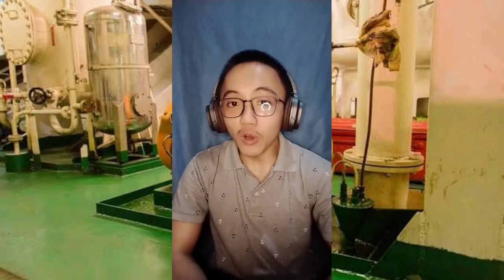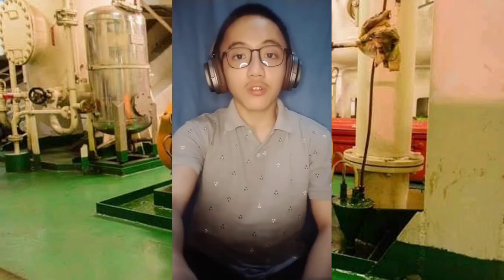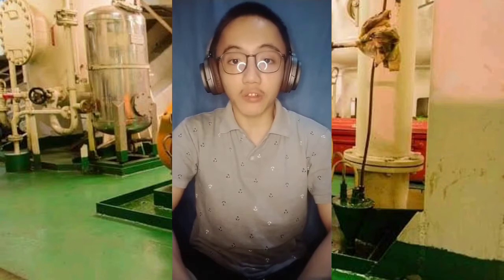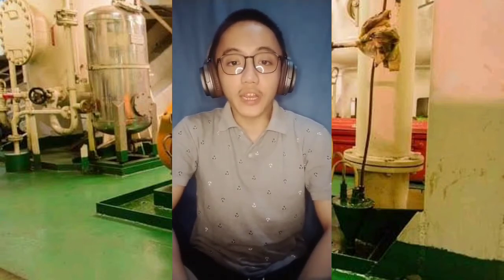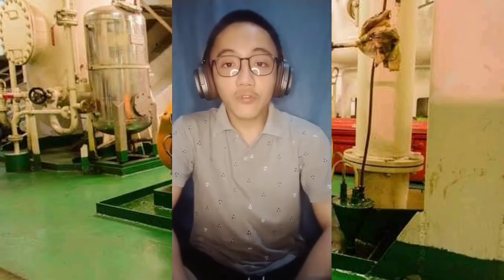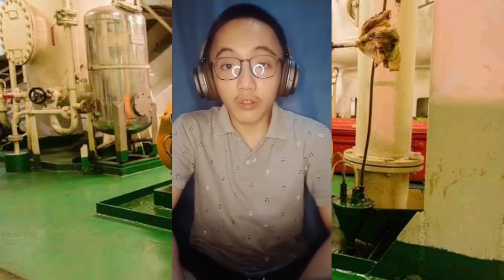So, kapag hindi pa ito bukas, buksan na rin natin. So, ang fifth step naman natin, to check if the following valve are closed and the air bottle delivery valve is closed too. So, the sixth step would be to check the control valve on the distributor close. So, the next step would be to switch the power to start the compressor. So, the eighth step would be to close the unloader valve. After you've done the procedure, you should wait until the pressure reach 10 kg force per square centimeter.